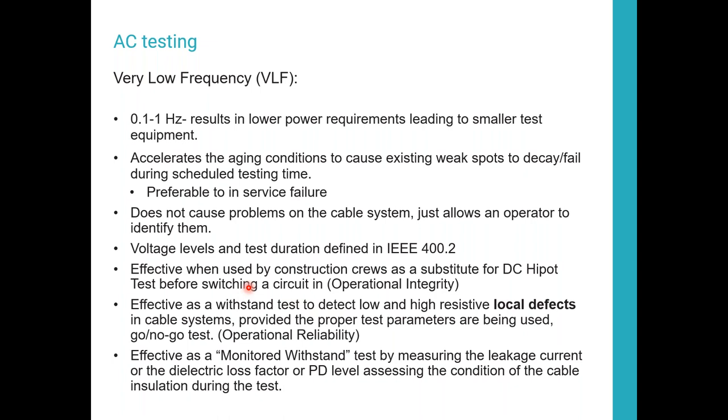It's effective when used by construction crews as a substitute for DC hipot tests. It's very similar equipment-wise to a DC hipot test. So it doesn't take an extreme amount of experience or training. It does take training, but it's not extreme like you used to have to do with spectrum analyzers and all to do the test. So it makes it practical for field testing. The test equipment is smaller in size based on the voltage level you need to apply. So typical medium voltage, it's going to be a portable unit. It's going to be something that a couple guys can carry around and bring to a site.